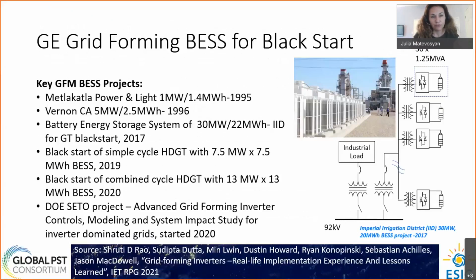there are a number of grid forming batteries that GE has deployed. Two of them on the list here are for microgrid application, the oldest being for the Metlakatla community in Alaska. So this is just a pure microgrid application. In Vernon, California, this application is to increase reliability of supply for industrial load. So at times this battery is operating in grid connected mode, and at times it's powering up that local load in islanded mode.